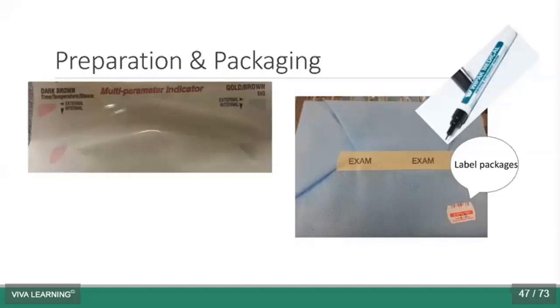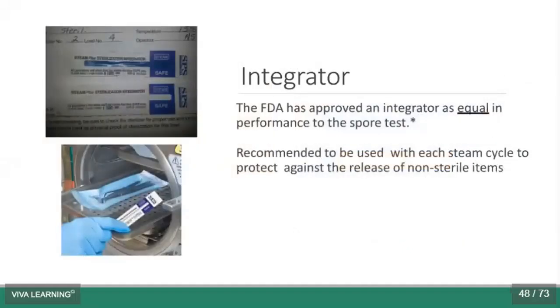I do see offices that'll use Sharpie markers, and sometimes they'll tell me, oh, but it's non-toxic, and I have to advise them against it. As one sterilizer manufacturer told me, they just don't know long-term what that constant exposure to that vaporized ink in the sterilizer might do to the actual sterilizer, and that it might void your warranty on that sterilizer, right? I mentioned earlier that I'm a big fan of integrators.